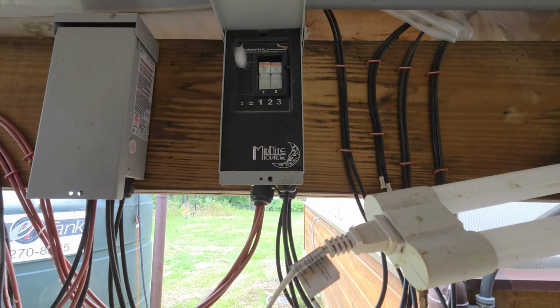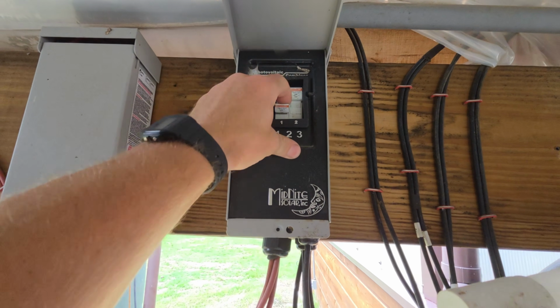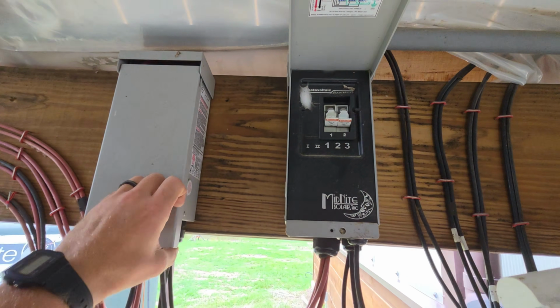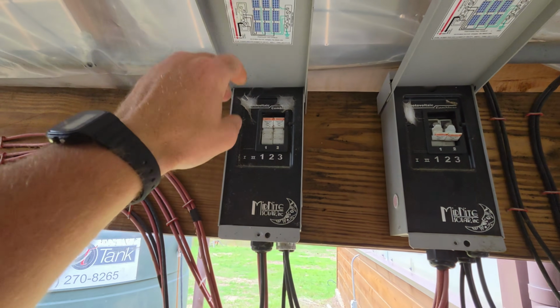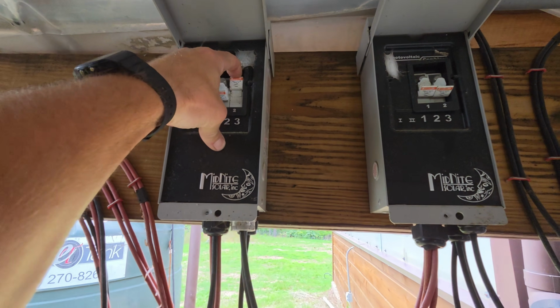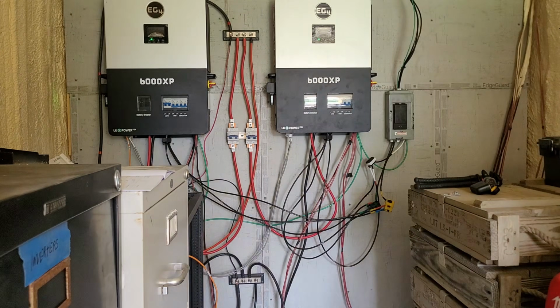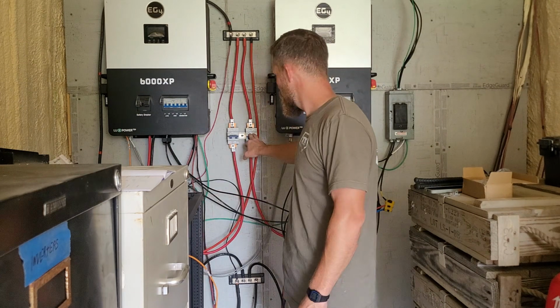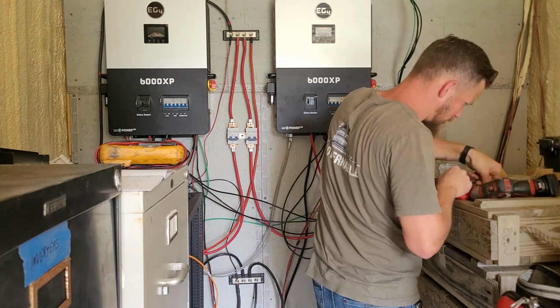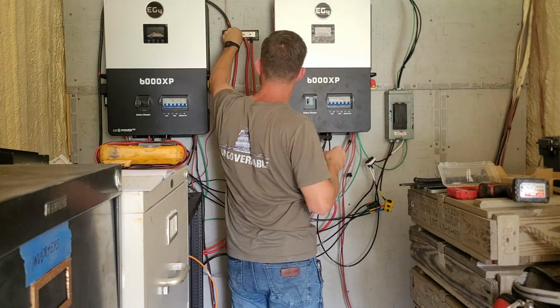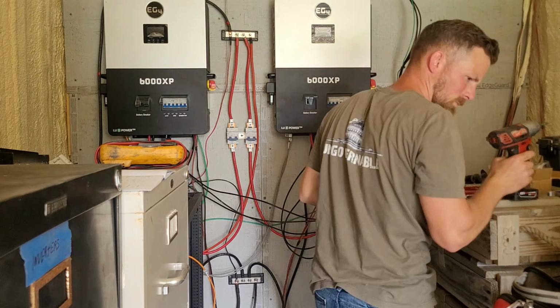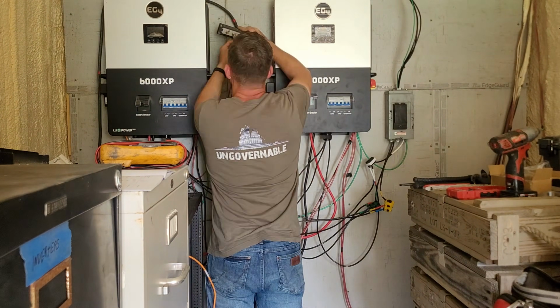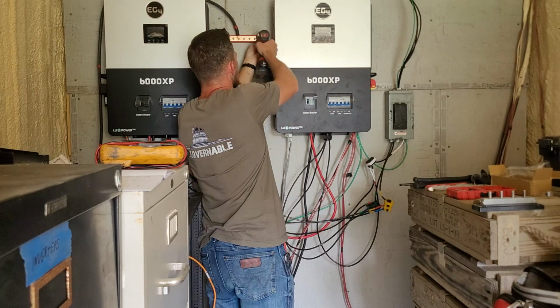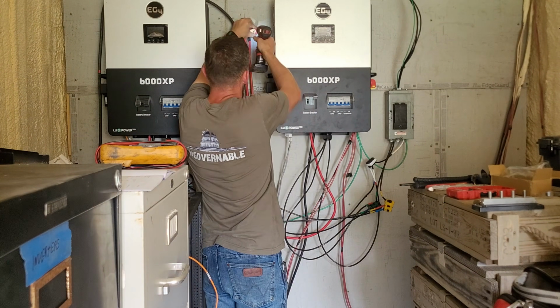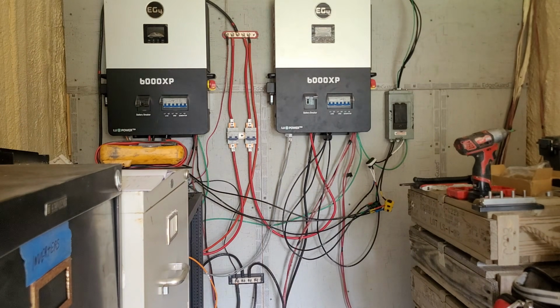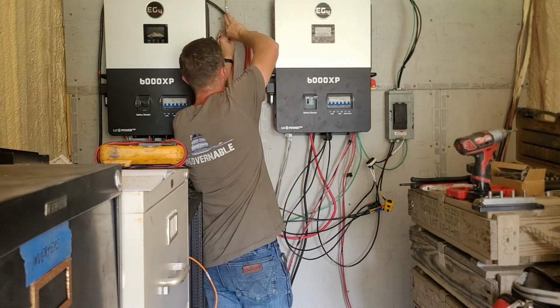I'm starting out here disconnecting my PV input. I've got 4 strings of panels coming into my EG4 6000 XPs. I'm going to disconnect the PV power, then follow the procedure in the manual for disconnecting and turning off these inverters properly. It's imperative you turn these off and re-energize them exactly as the manual describes, or you will blow a capacitor or something along those lines.